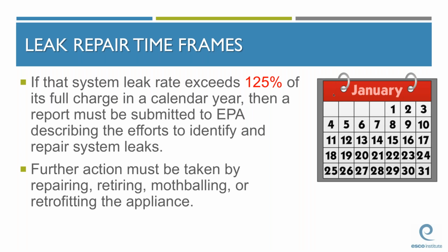We get questions about this rule all the time. And yes, a system can have an annual leak rate that exceeds its total charge. This happens when the system is recharged or topped off multiple times throughout the year. It's strongly recommended that this be made perfectly clear to your students to avoid any confusion. Like I said, we do get a lot of instructors that seem to be confused about a leak rate of 125%. So if our fellow instructors are confused with that, I can guarantee you that a lot of our students are as well.